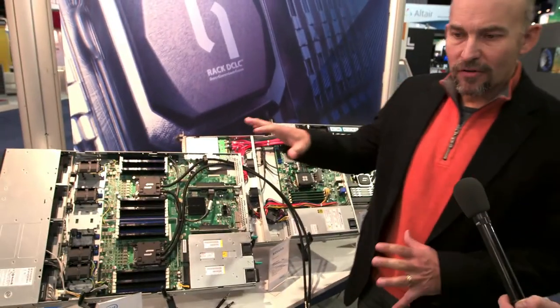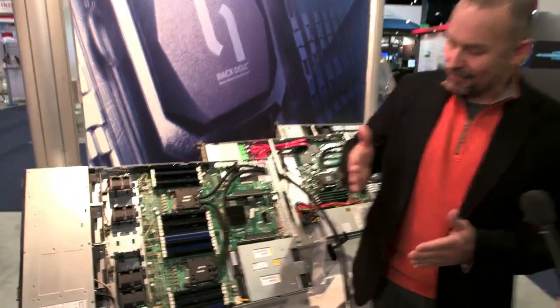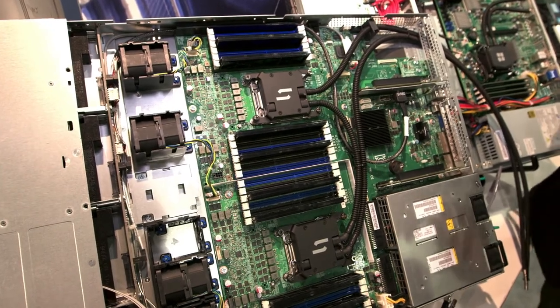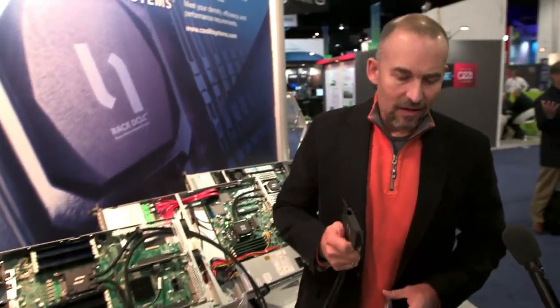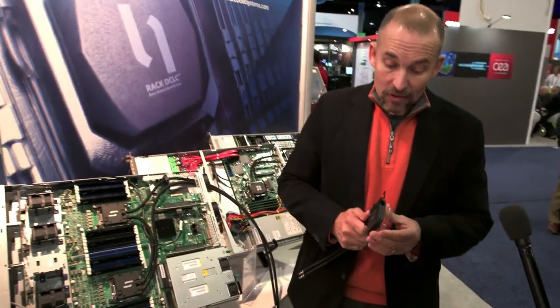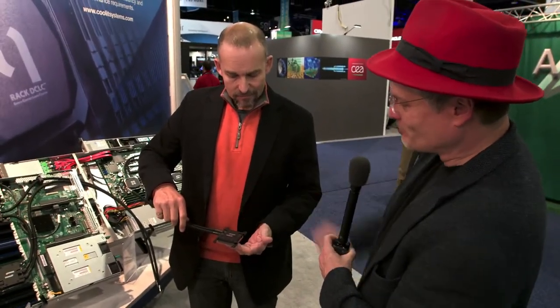Sure thing. This year, what's new for us is we've moved to a centralized pumping scheme. We have created a very low-profile cold plate — that's the copper plate that has very small micro channels built into the system. It transfers the heat from the processor directly into the liquid. Since there's no pump in here anymore, we can go to a very narrow construction — it's only 15 millimeters tall. That makes it simple to integrate into compact form factors like blade servers or twin configurations. It used to be almost double the height. Some of the advantages liquid cooling provides is increased density, and that means blades that are smaller, more narrow, and more compact.